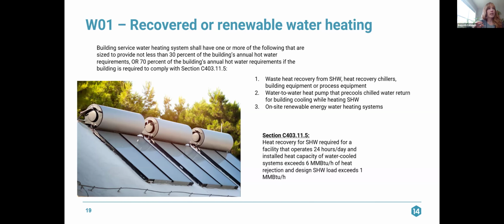Okay, so what recovered or renewable water heating technologies count towards W01? It's waste heat recovery from heat recovery chillers for preheating of service hot water, or process waste heat from process equipment. A water-to-water heat pump that pre-cools chilled water return for building cooling while heating service hot water, or on-site renewable energy water heating systems. We have a little example of that there, that solar hot water.